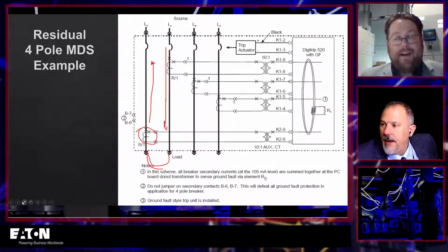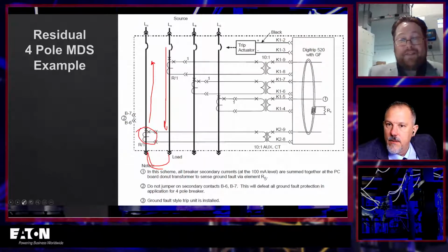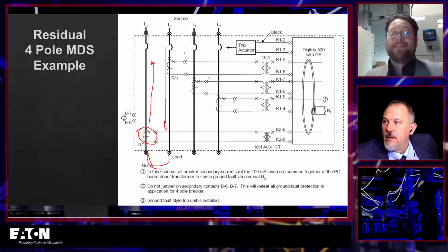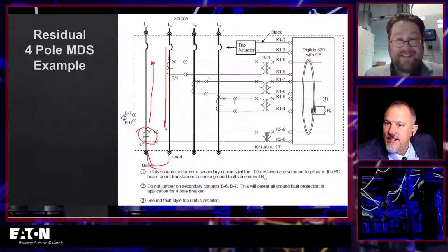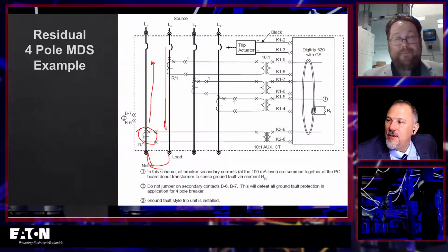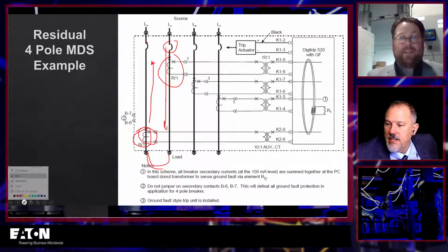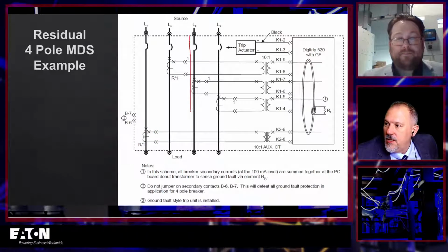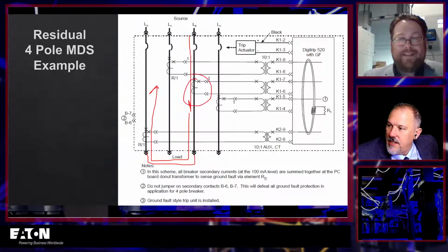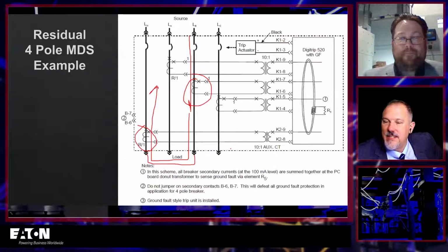Okay. So that's two, maybe three tests for phase A. And then we're going to do that for phase B, then for phase C. Because you've confirmed that this CT is the right direction in relation to this one. And then you're going to set it all back up again. You're going to run this current through there, and then run this current up through there. And now you know that this CT is in the right phase direction with respect to that CT. And then you're going to do phase C the same way.